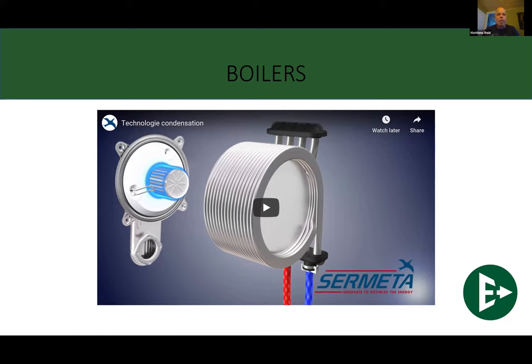One thing I have come across in the past is that these type of heat exchangers are pretty prone to what I believe the whole industry refers to as coffee grinds. You take the burner plate off, you look inside the heat exchanger burner tube, and you're going to see what looks like coffee grounds along the bottom of the heat exchanger. The reason that happens, 10 chances to one, is usually cross-contamination of the intake flue gas, where it's getting a bit of the recycled exhaust coming back in and gets reburned. That's usually a good indicator that you're getting some of that.